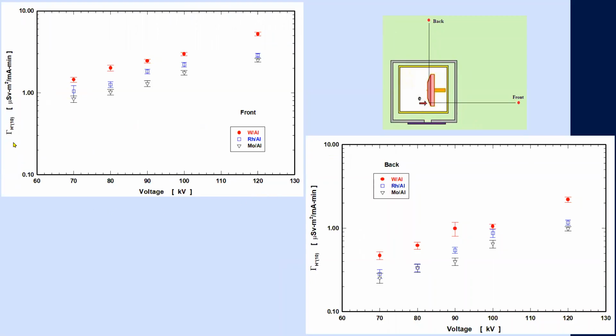So here I'm showing you the gamma factors for the ambient dose equivalent in both cases, but due to the X-rays that leak out from the shielding of the X-ray tube. In the front, which is 1 meter from the focal spot, here are the values, and we can notice that as the voltage increases, the gamma factors for these leaking photons also increase. Also, if we change from tungsten to rhodium and from rhodium to molybdenum, this gamma factor decreases. Notice here that the units are in microsievert, which means three orders of magnitude lower than the gamma factors obtained in the useful beam.